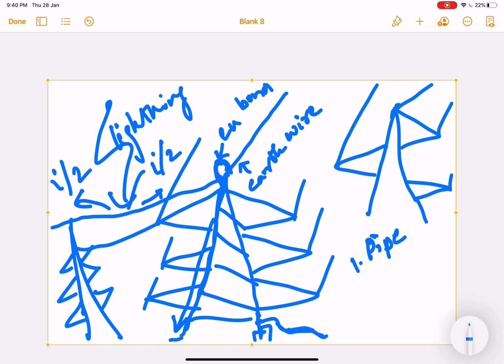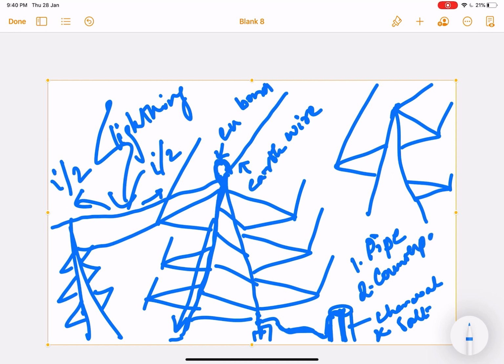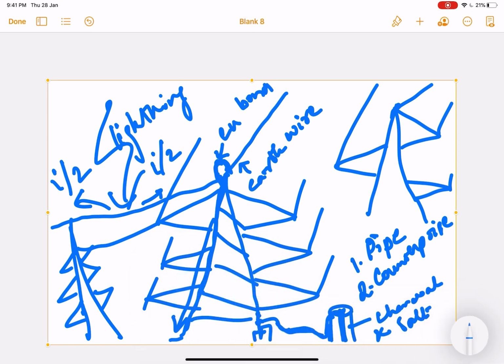In pipe type earthing, at a distance we dig a pit, and we fill it with a mixture of charcoal or coke and salt, and a steel pipe of a specific diameter is inserted in the middle. Because the soil is good, it will be earthed properly through this pipe type earthing. Next is counterpoise earthing, used where the soil resistivity is on the higher side, which usually happens when the earth is rocky.